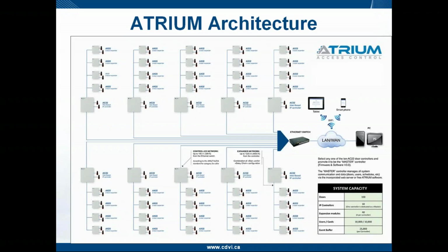So for the end user, they might call you up as a service tech and say, my reader is beeping every 3 seconds and I don't know why. And that is one of the things that when the expander goes offline, both readers will flash red every 3 seconds along with a chirp, to indicate that there is something not functioning properly at that particular controller or expander, I should say.